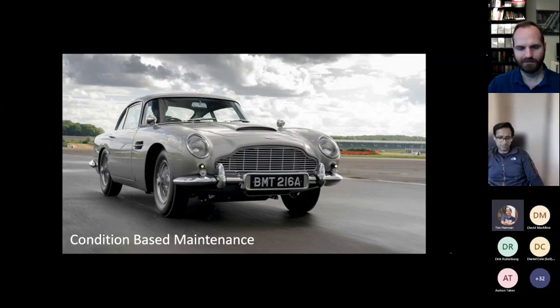If I speak to the manufacturer, they'll say the tyres need to be replaced every 2 years or every 20,000 miles — an expensive piece of tyre to replace. If I take a condition-based maintenance approach instead, I get myself a tyre gauge and I know I need to change those tyres when the tread is only 3 millimeters.